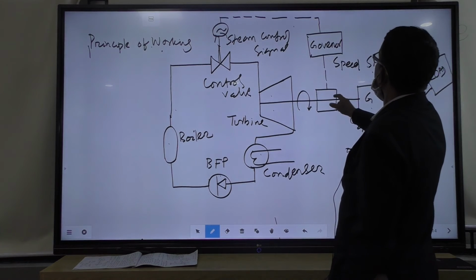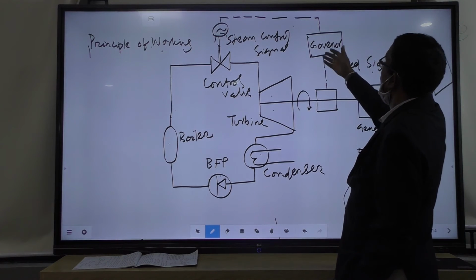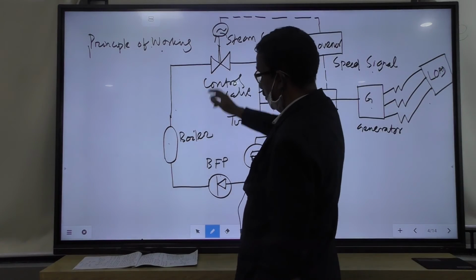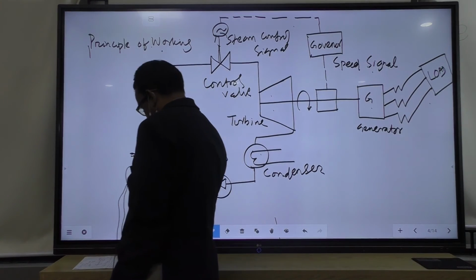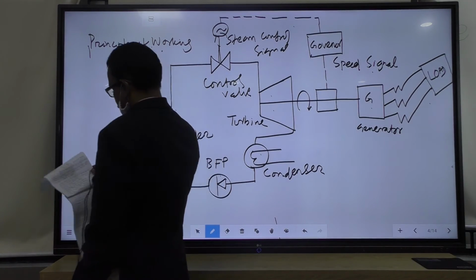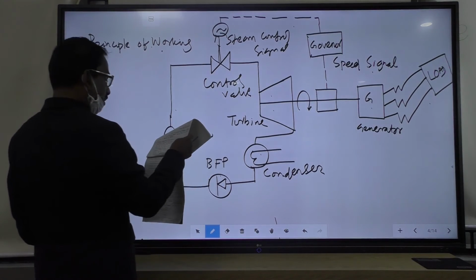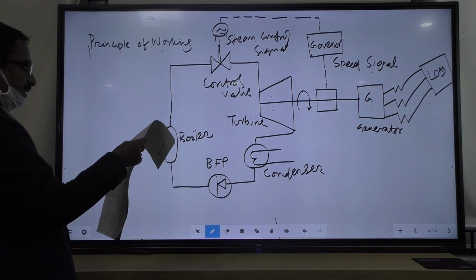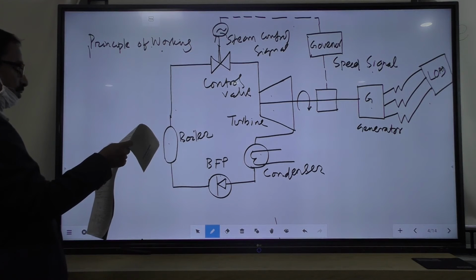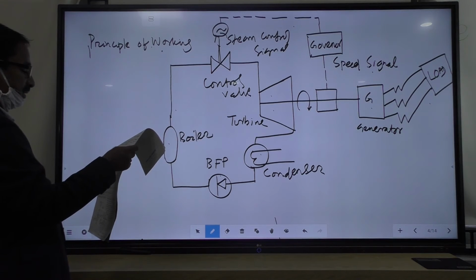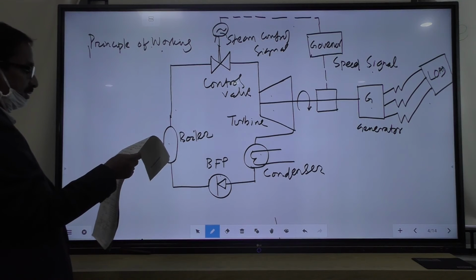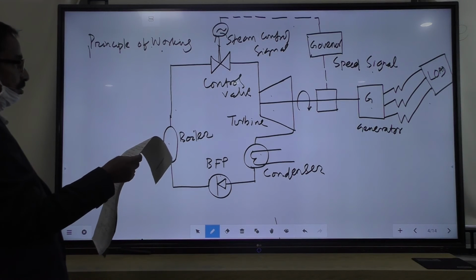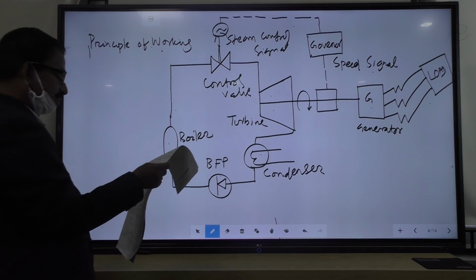This is the speed sensor at the governor; when the speed changes, the valve opens or closes accordingly. Similarly, if the load is increased, the speed of the turbine starts decreasing. To bring the machine to its normal speed, the steam valve is opened to allow more steam. More steam is needed when the load increases, so we need more steam.